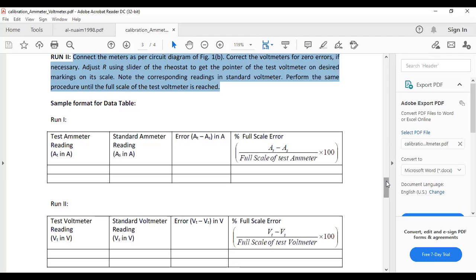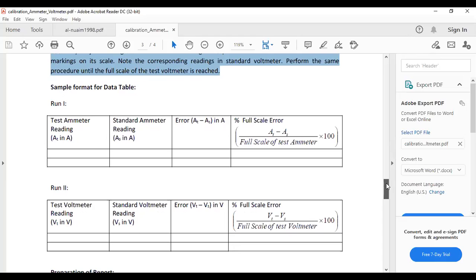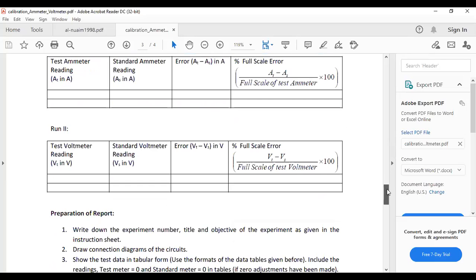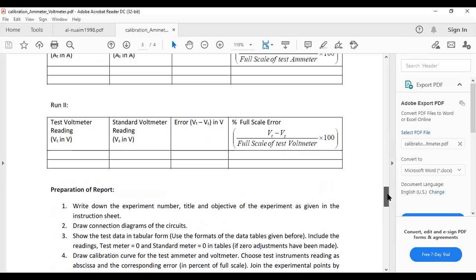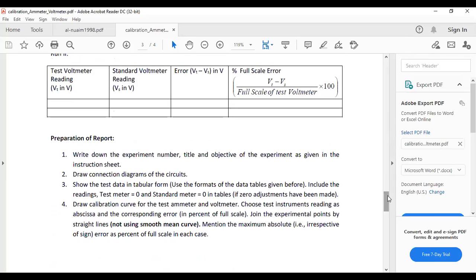If the test ammeter range is 5, we have to divide it by 5. For all these discrete readings, we have to divide it by 5 only. So this is how we can determine the percent full scale error. Similarly, for voltmeter also, we can calculate the actual error and the percent full scale error. And this is the report part.